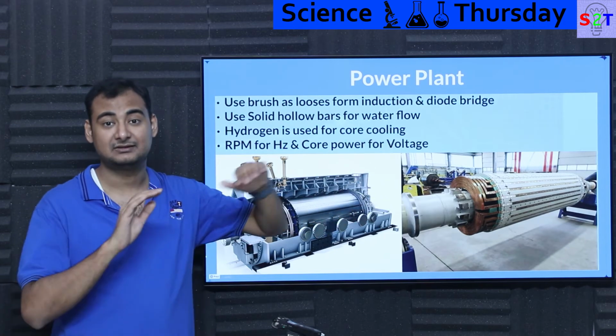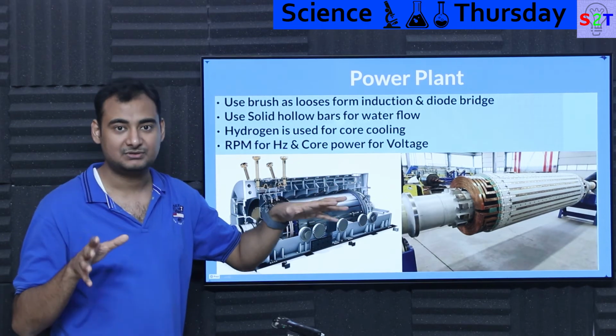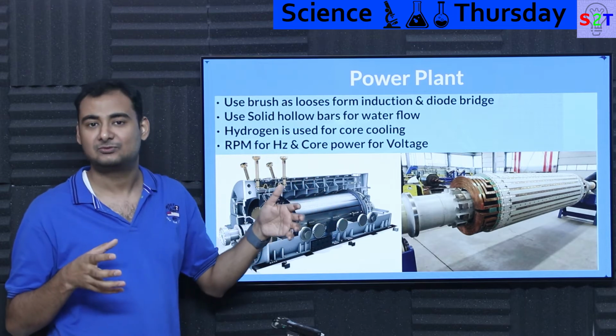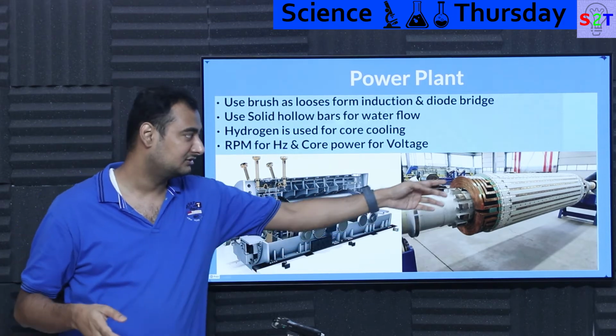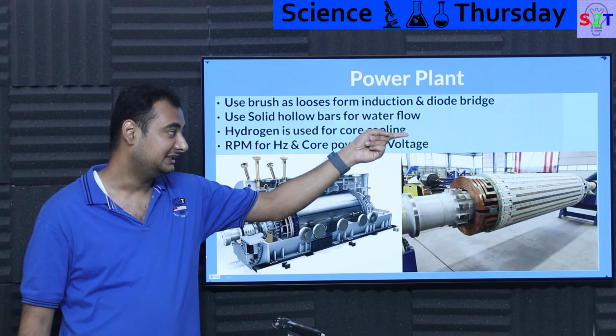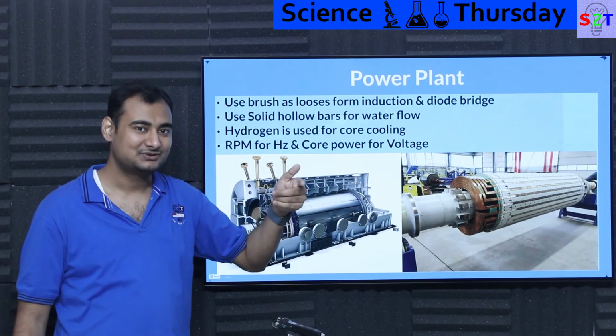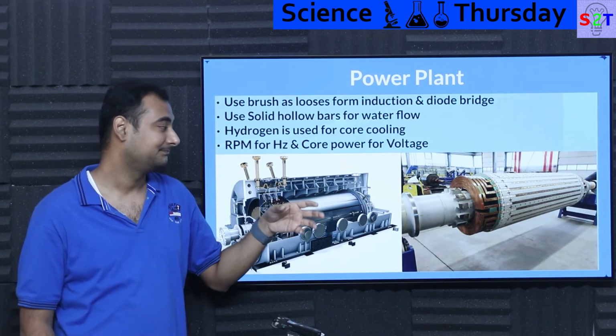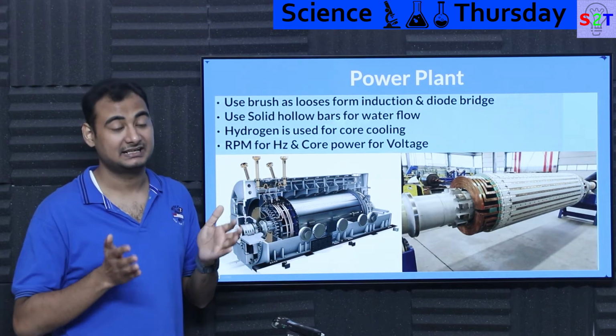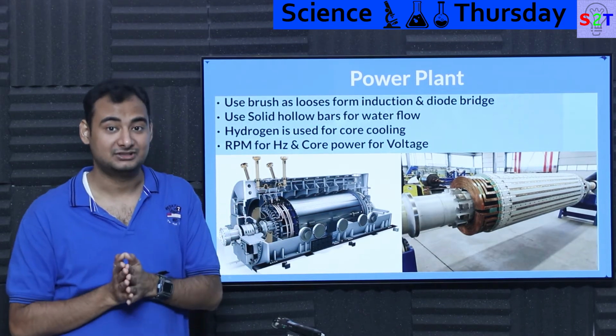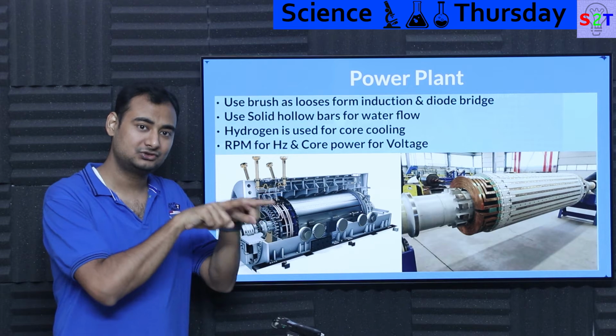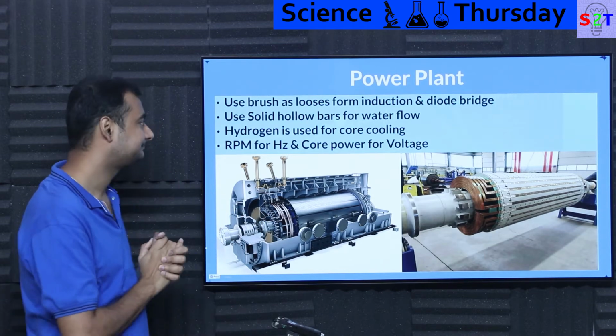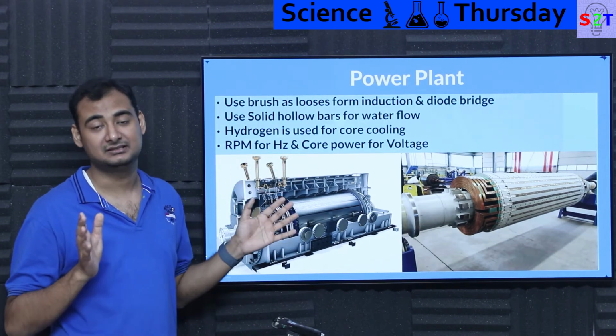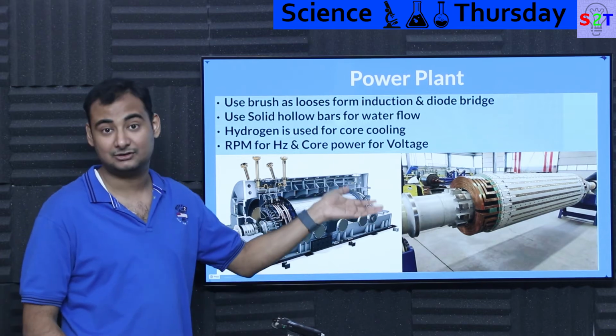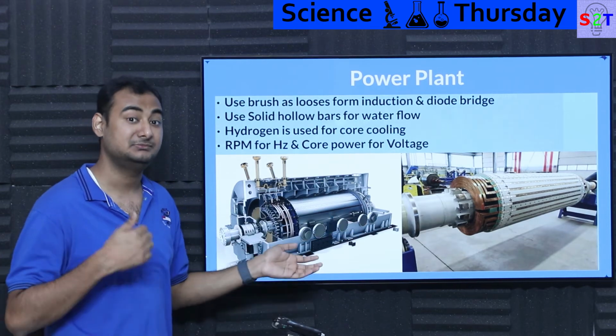Yes, this exciter current is nowhere near a big percentage of the main generator output. The main generator output could be, let's say, 100 megawatts. This will barely see 10 megawatts. But here's the deal: even if it's 1 megawatt, 1 or 2% of 1 megawatt is a lot of energy. So for that reason, people may simply say, okay, losses from brushes are far more desirable, because rather than having a 2-step loss, we can just have a 1-step loss. So that's the best understanding I can come up with. That's why all power plant generators are generally brushed.